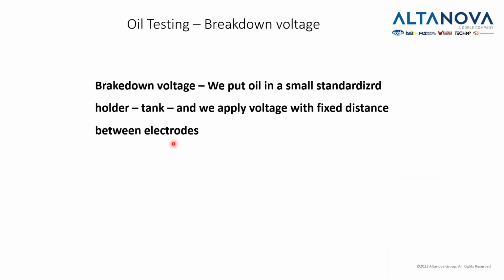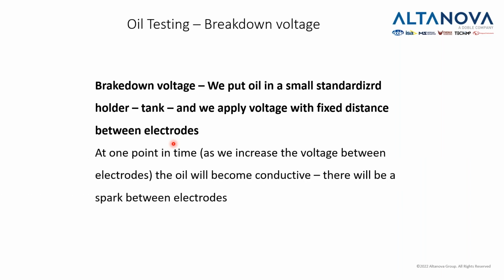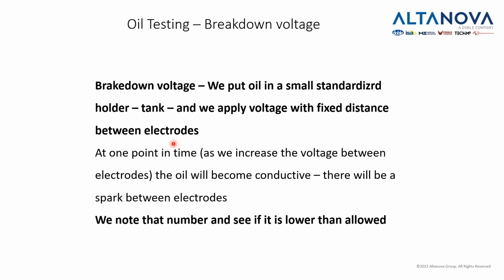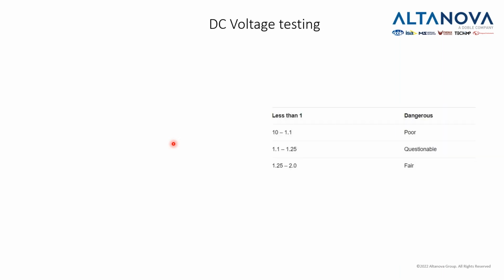What we do have still time to mention is the breakdown voltage. How do you do a breakdown voltage test? It's one of the most basic tests. You take a sample of the oil, you put it in a standardized holder in a tank, and we apply high voltage with a fixed distance between electrodes. At one point in time, as we increase the voltage between electrodes, the oil will become conductive, and there will be a spark between electrodes. We note that number and see if it's lower than allowed. Of course, excuse me, that number needs to be as high as possible, because we are testing the insulating properties of our oil.